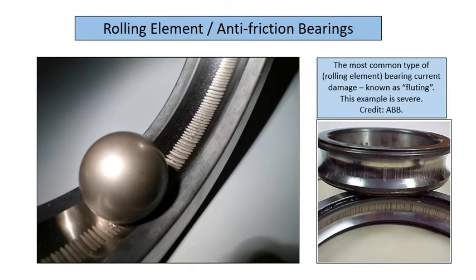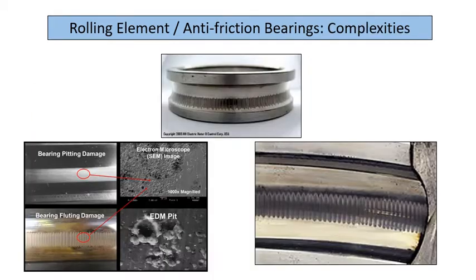Okay, there's typical damage from fluting. You've seen it already. And there's the different types again. This is what you can have. You can often have bearing currents due to other defects. And what's happened here? Well, you've got a heavy axial thrust or something that's caused this bearing to run for its load angle to be tremendously out, as well as shaft currents. And this here, you can see a certain amount of misalignment in the bearing, the way the line is not exactly symmetrical.